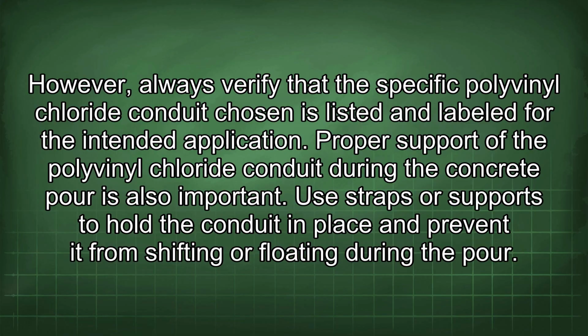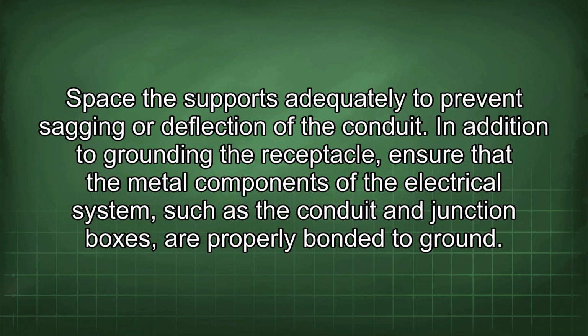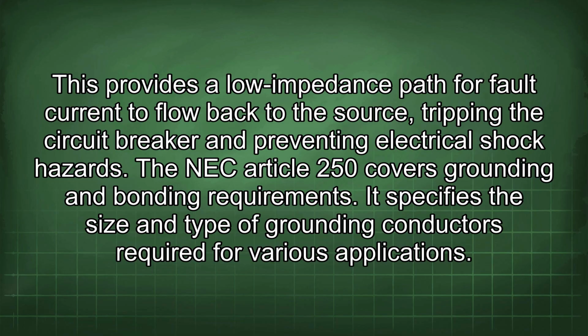Proper support of the polyvinyl chloride conduit during the concrete pour is also important. Use straps or supports to hold the conduit in place and prevent it from shifting or floating during the pour. Space the supports adequately to prevent sagging or deflection of the conduit. In addition to grounding the receptacle, ensure that the metal components of the electrical system, such as the conduit and junction boxes, are properly bonded to ground. This provides a low impedance path for fault current to flow back to the source, tripping the circuit breaker and preventing electrical shock hazards. The NEC Article 250 covers grounding and bonding requirements. It specifies the size and type of grounding conductors required for various applications.